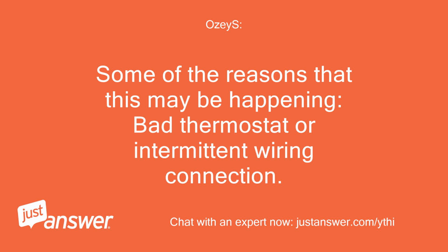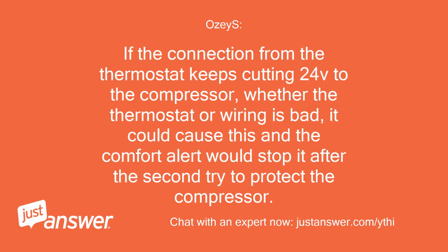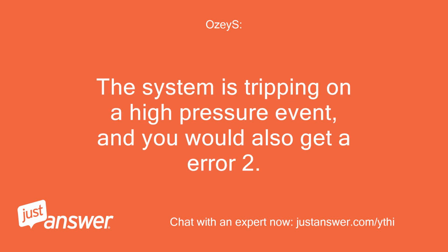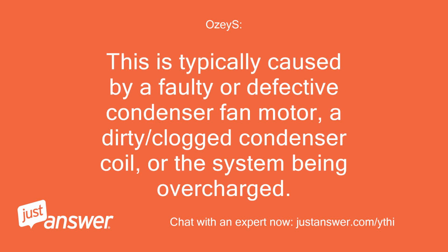Some of the reasons that this may be happening: bad thermostat or intermittent wiring connection. If the connection from the thermostat keeps cutting 24V to the compressor, whether the thermostat or wiring is bad, it could cause this, and the Comfort Alert would stop it after the second try to protect the compressor. The system is tripping on a high pressure event, and you would also get an error 2. This is typically caused by a faulty or defective condenser fan motor, a dirty/clogged condenser coil, or the system being overcharged.